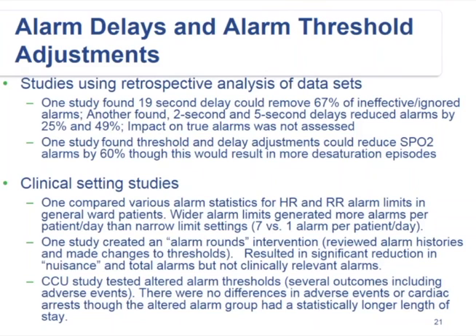While a different study found that by implementing 2 to 5 second delays, you could also reduce alarms by significant amounts, 25 and 49%. Unfortunately, neither of these studies actually studied the impact of whether there were missed true alarms. A different study found that threshold and delay adjustments combined together could reduce pulse ox alarms by 60%. Unfortunately, they also found that this strategy actually would cause a certain number of true desaturation episodes to be missed.